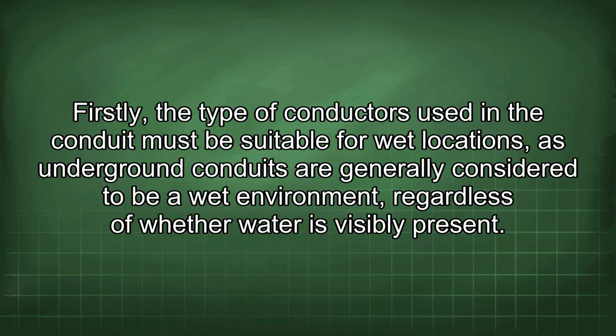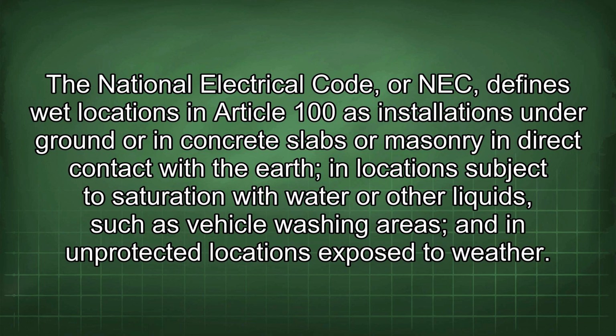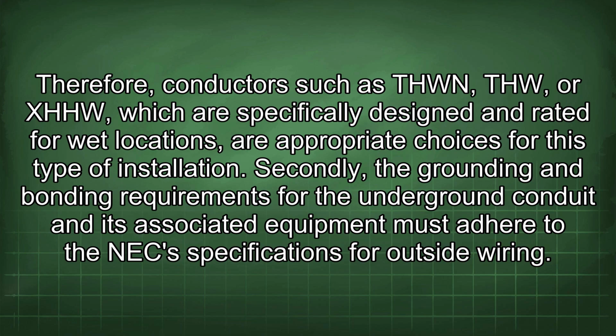method. Firstly, the type of conductors used in the conduit must be suitable for wet locations, as underground conduits are generally considered to be a wet environment, regardless of whether water is visibly present. The National Electrical Code, or NEC, defines wet locations in Article 100 as installations underground or in concrete slabs or masonry in direct contact with the earth, in locations subject to saturation with water or other liquids, such as vehicle washing areas, and in unprotected locations exposed to weather. Therefore, conductors such as THWN, THW, or XHHW, which are specifically designed and rated for wet locations, are appropriate choices for this type of installation.